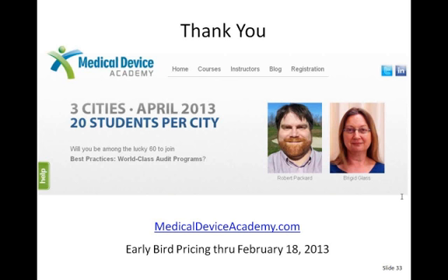That's something that I find a lot of companies get in trouble with the FDA because they're making a claim on their website that is not approved or not cleared by the FDA. It's making a claim they're not allowed to make. They don't have evidence for it, or it's exceeding the 510(k) terms. I have experienced that one other time with a notified body, but it's rare for notified bodies, though it might change in the future. So the solution, the CAPA that almost always gets written, is regulatory will be part of the approval process of website changes.